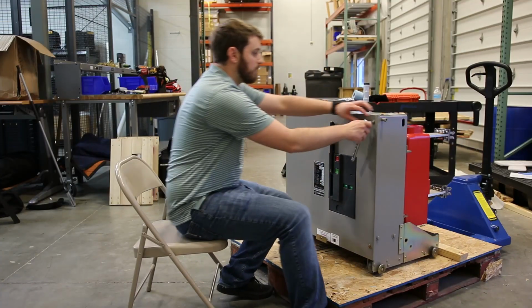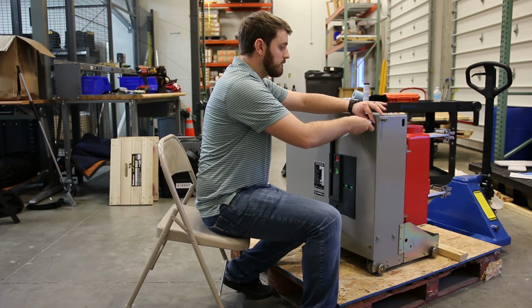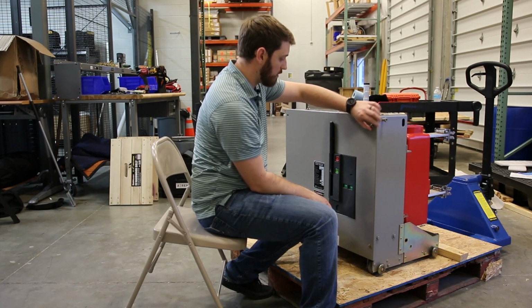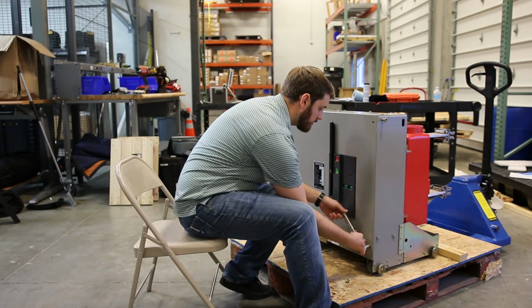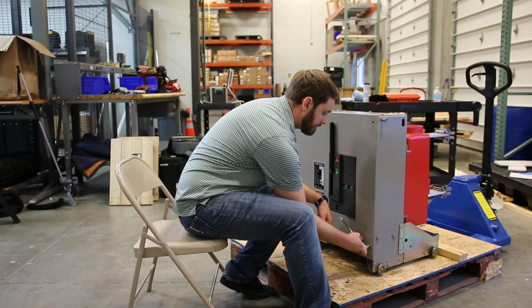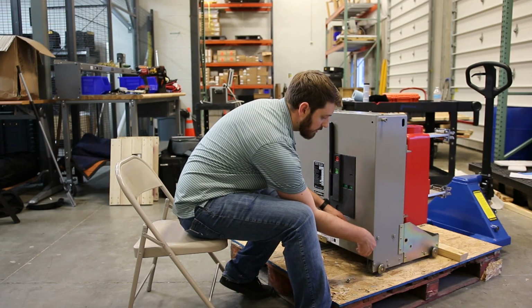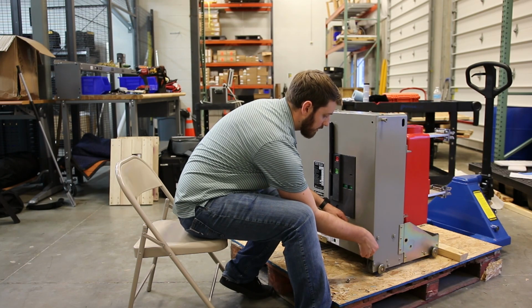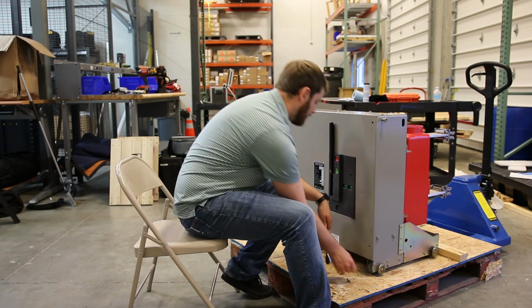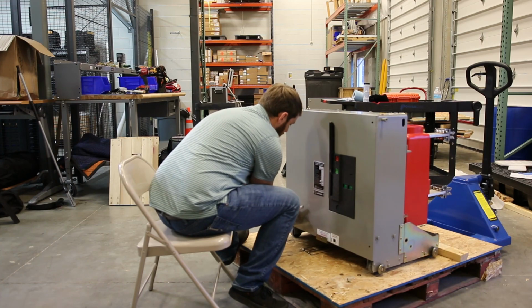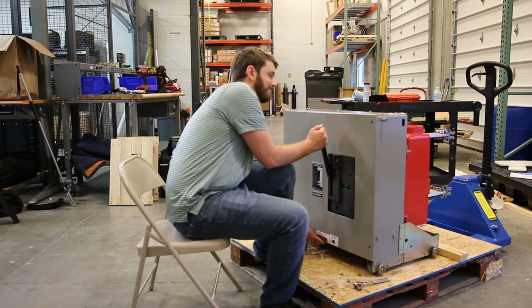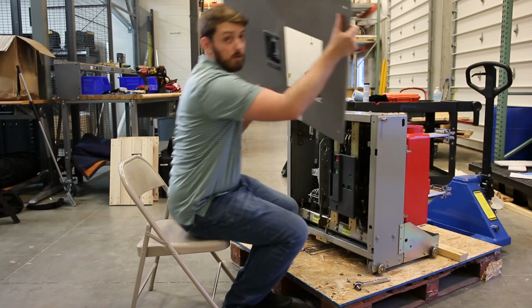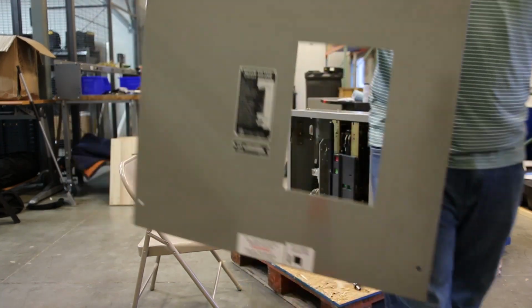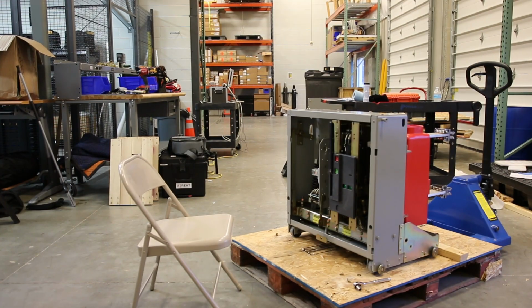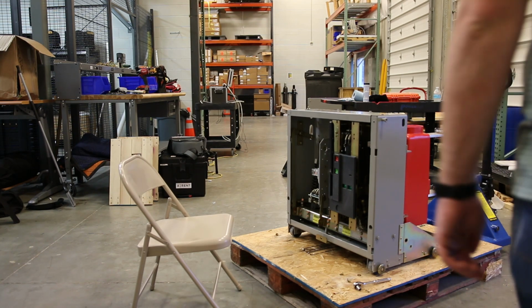All right, one of the first things that I want to do is take the cover off the breaker because we have to inspect the internal mechanism for lubrication points. Obviously, evidence of damage, ingress of water, ingress of rodents, arcing, tracking, things like that we want to take a look at. We're going to pull our cover off. Nameplate's right there on the cover. That tells you everything you need to know about the breaker. Serial number, the trip and close voltage, stuff like that.